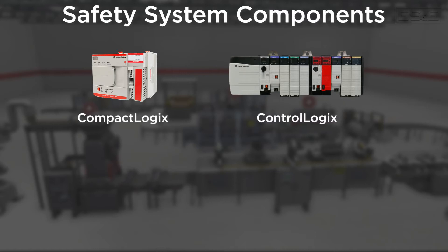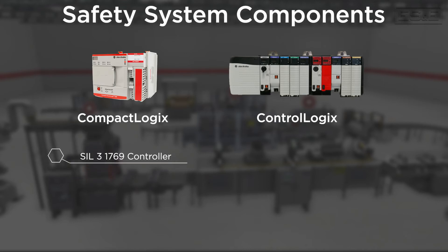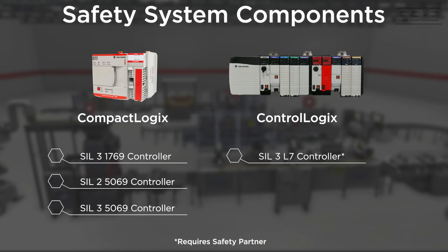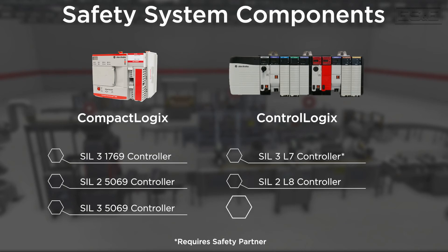The CompactLogix starts with the SIL-3 rated 1769 controllers, but it also encompasses the SIL-2 and SIL-3 5069 controllers. The ControlLogix also has two levels of controllers, which are the SIL-3 rated L7 controllers, which require a safety partner, and the second level is the SIL-2 L8 controllers or SIL-3 L8 with a safety partner.